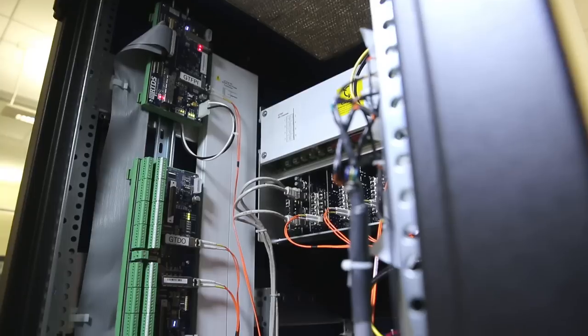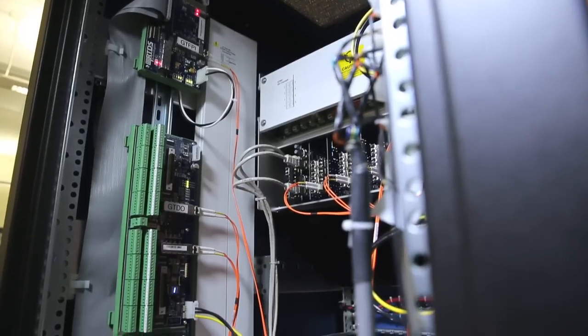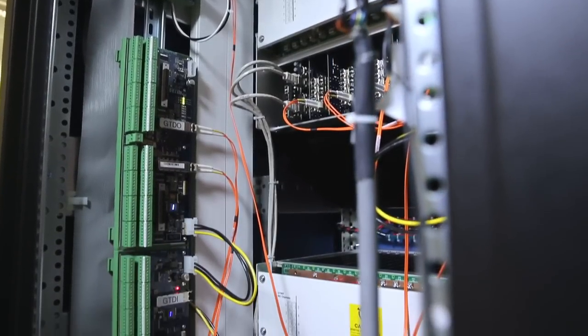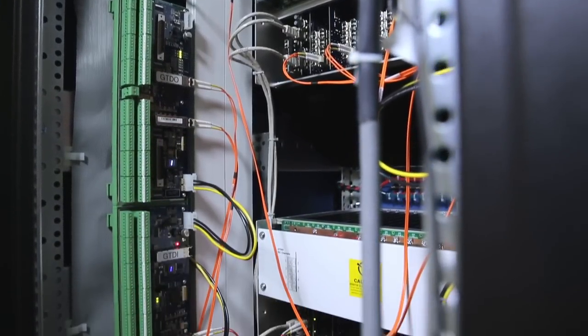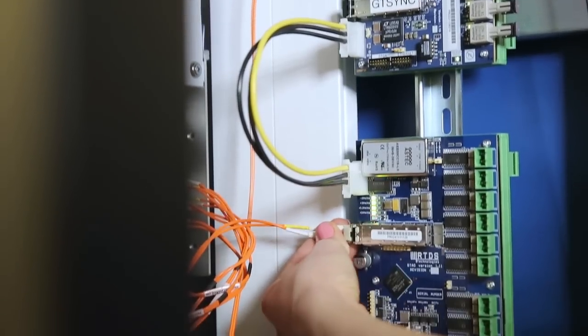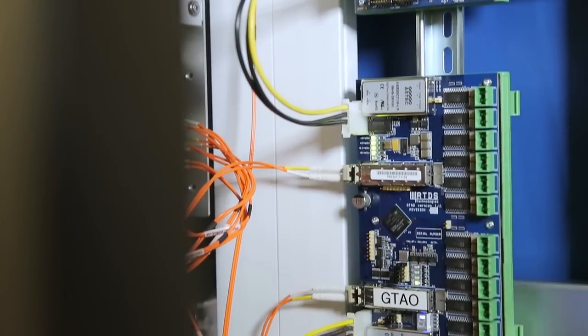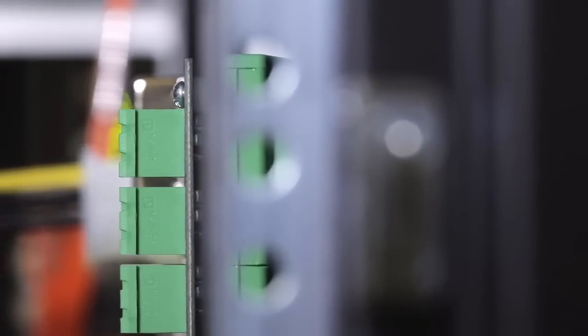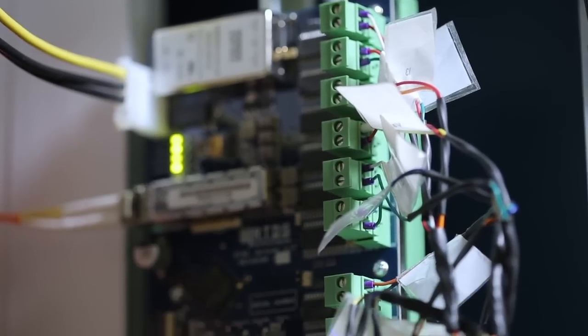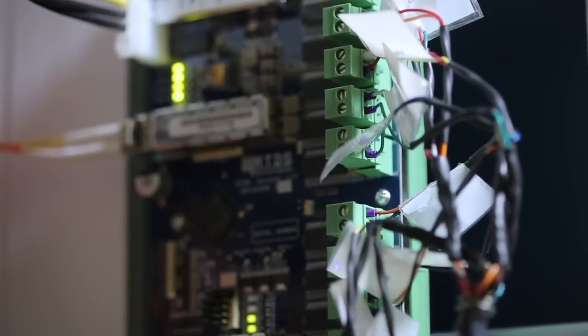The RTDS simulator's custom designed input output cards communicate with the simulator via fiber optic cable and provide optically isolated analog or digital output and input for interfacing with external equipment.